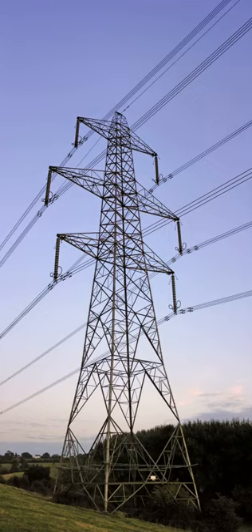For crossing broad valleys, a large distance between the conductors must be maintained to avoid short circuits caused by conductor cables colliding during storms. To achieve this, sometimes a separate mast or tower is used for each conductor. For crossing wide rivers and straits with flat coastlines, very tall towers must be built due to the necessity of a large height clearance for navigation. Such towers and the conductors they carry must be equipped with flight safety lamps and reflectors. Two well-known wide river crossings are the Elbe Crossing 1 and Elbe Crossing 2. The latter has the tallest overhead line masts in Europe, at 227 meters (745 feet) tall.